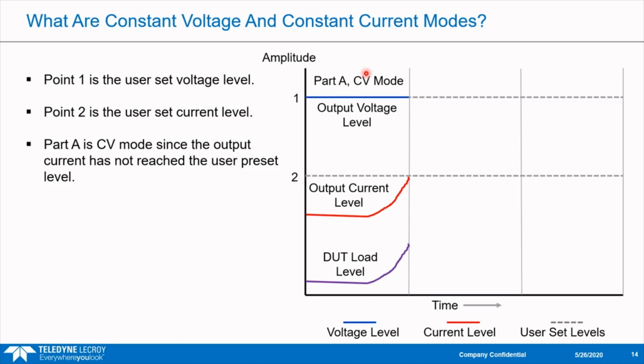So what's happening? We're in constant voltage mode. Our voltage is flat at the user set level because the DUT loading is relatively low and the current hasn't hit our user set level. When the current does hit the user set level, it stays there and the voltage drops, because the DUT load has increased, so the current hits its maximum and the voltage drops down.